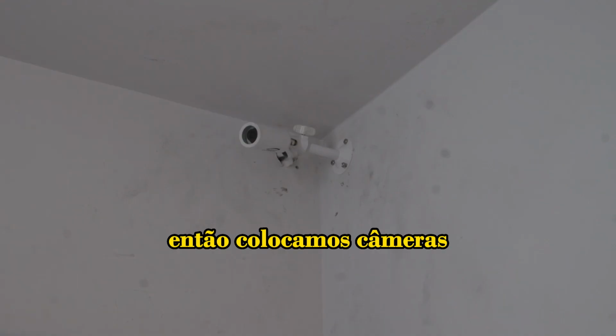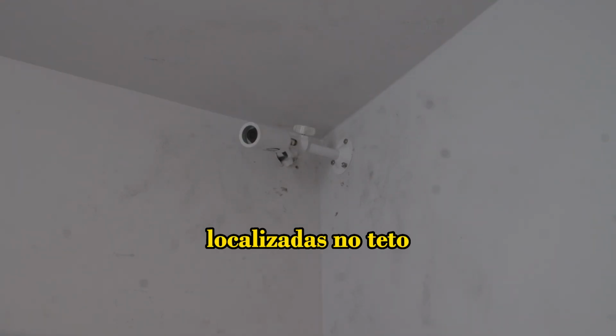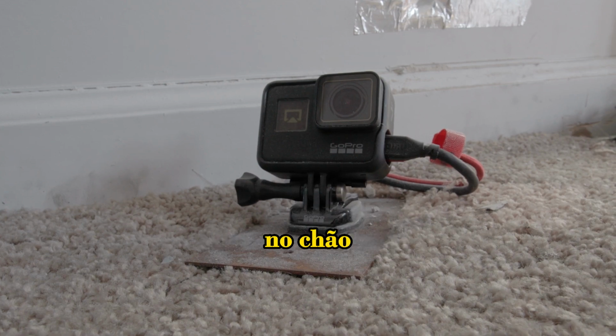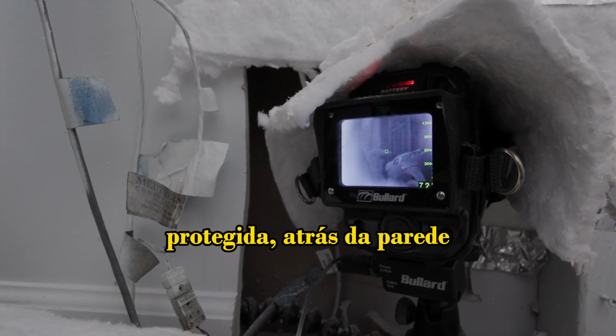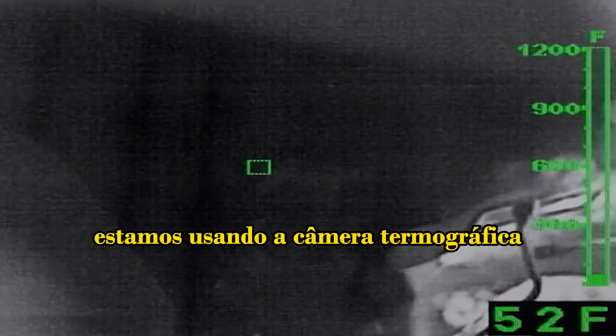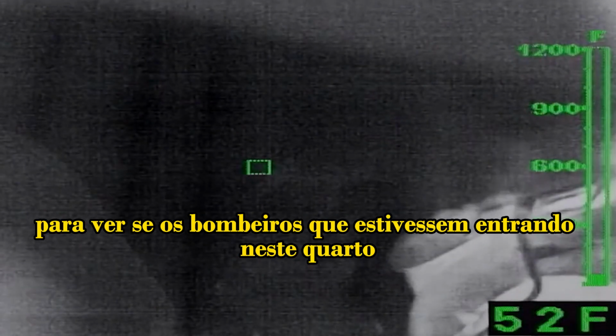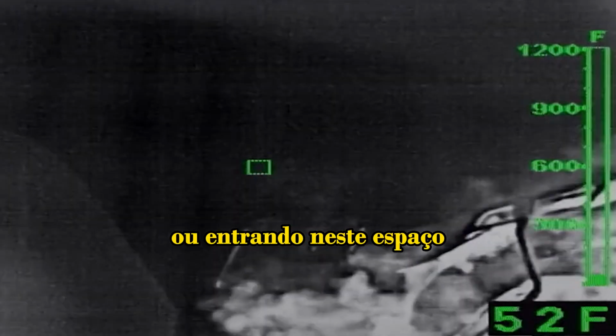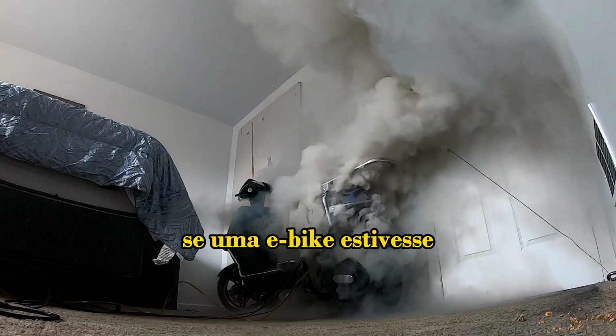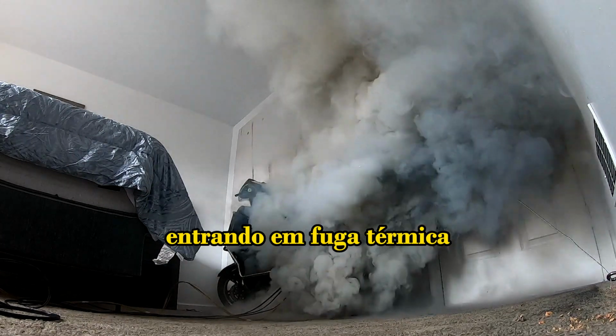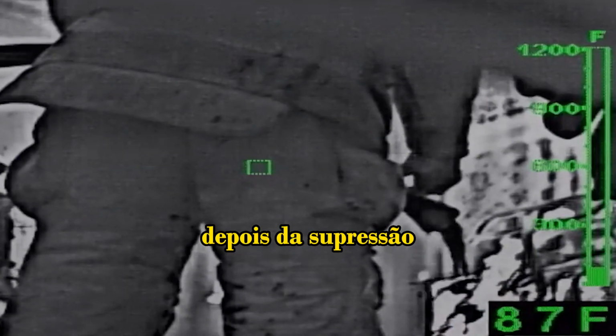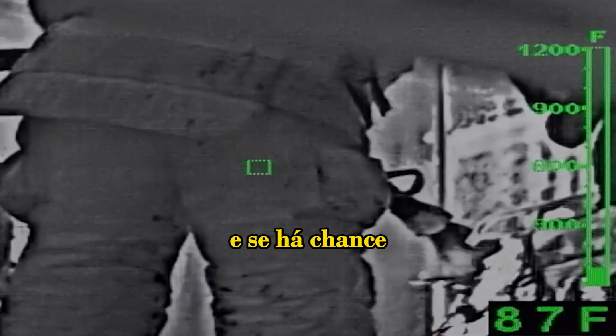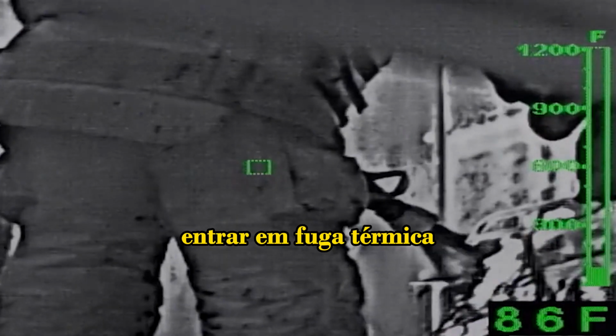So we have cameras located up high in the space, as well as down low where we have a thermal imaging camera protected behind the wall. We're using the thermal imaging camera to see what a firefighter entering the room might see if a bike was going into thermal runaway, or potentially after suppression, if it was still hot and had the opportunity to go into thermal runaway again.